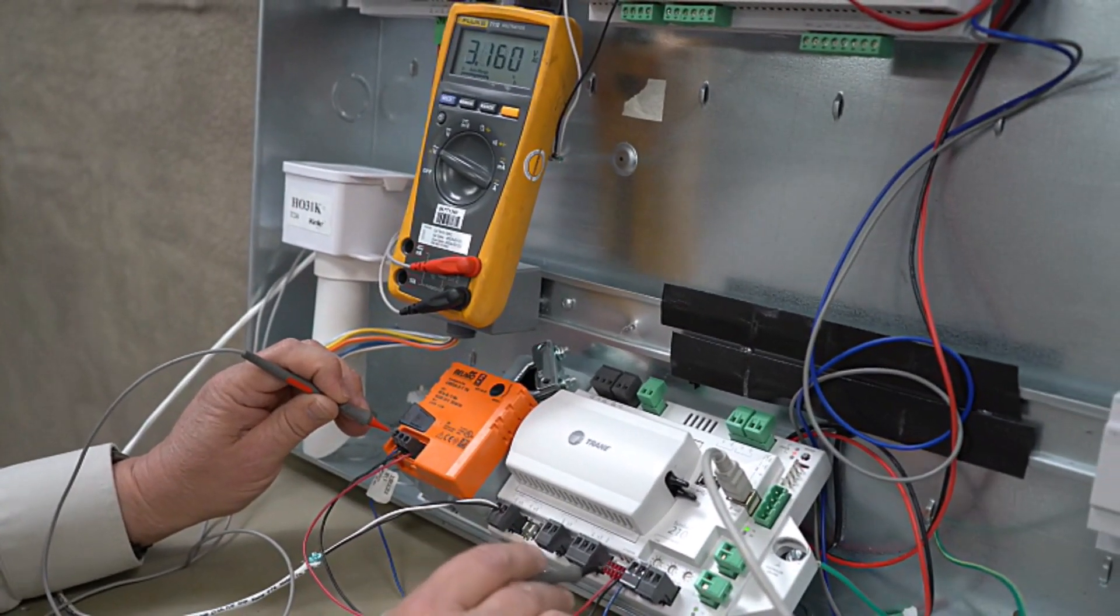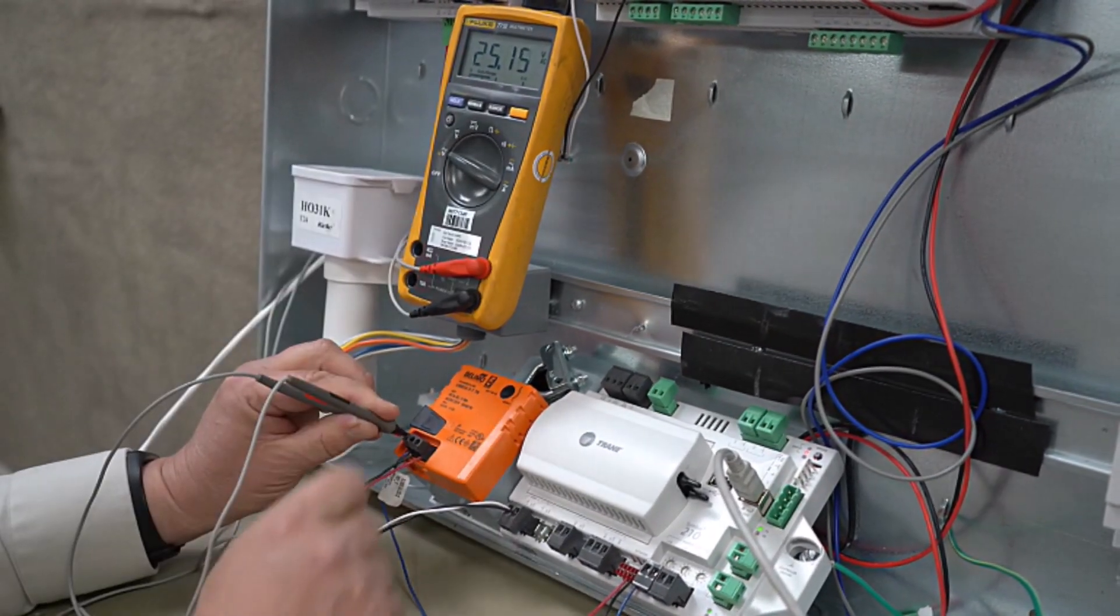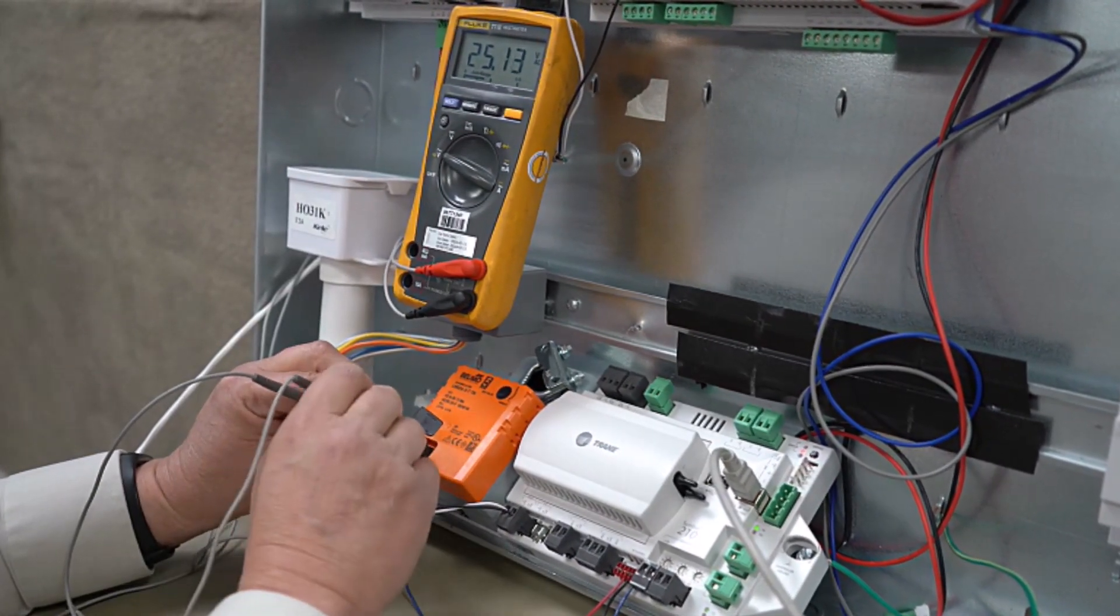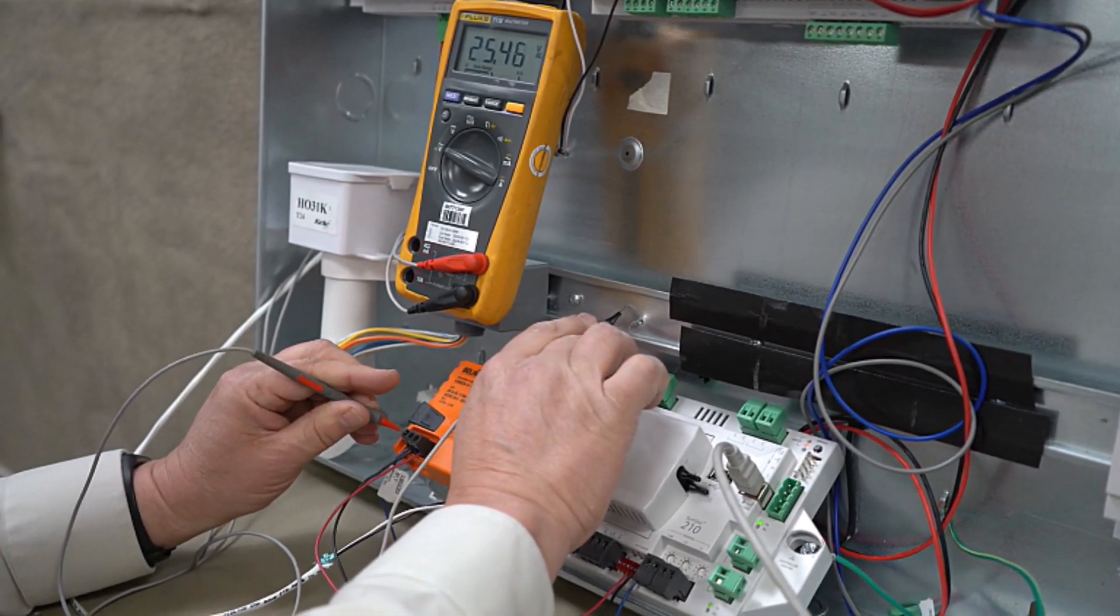So our actuator just came on. It's driving. We can see we get the full 25 volts across there for that voltage drop across here. But as we measure each leg to ground, there's the 25. That's our hot leg coming in.